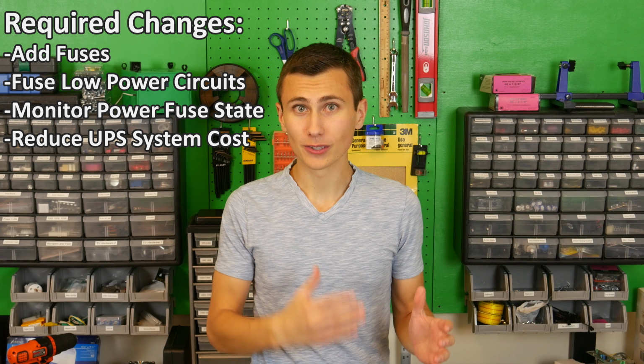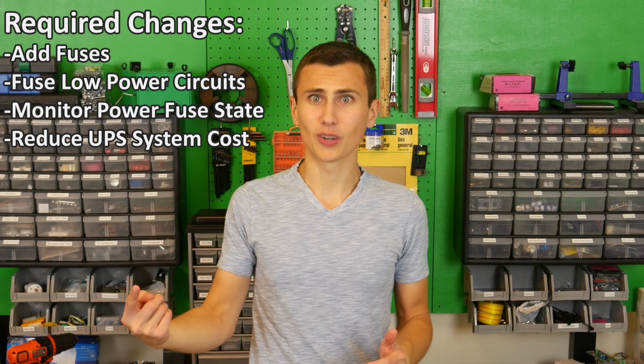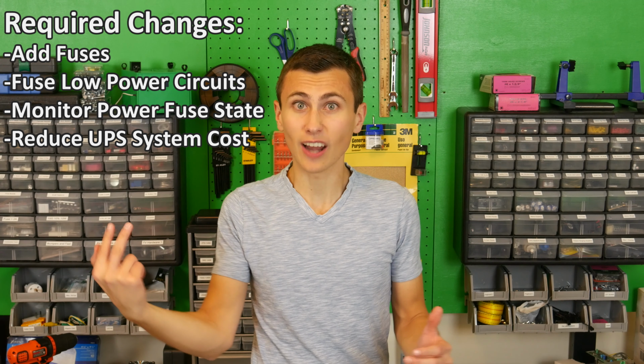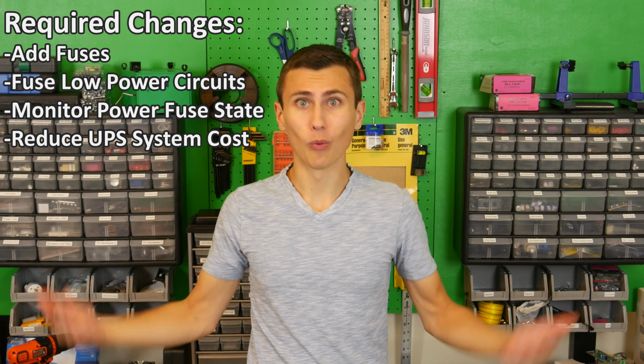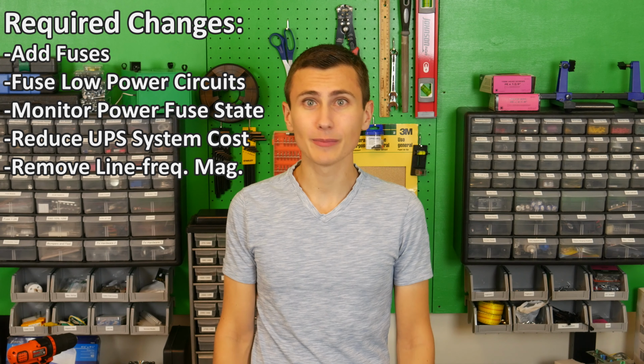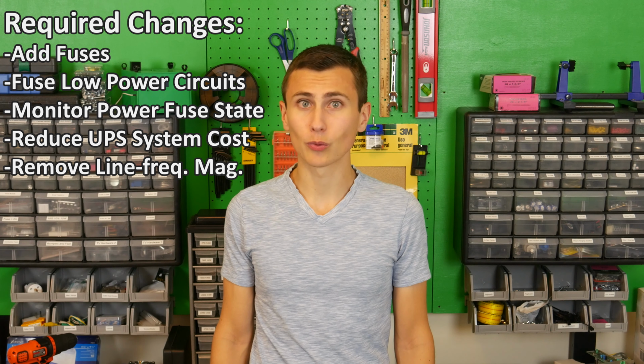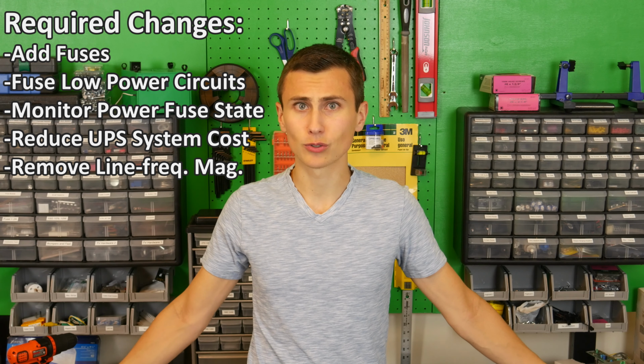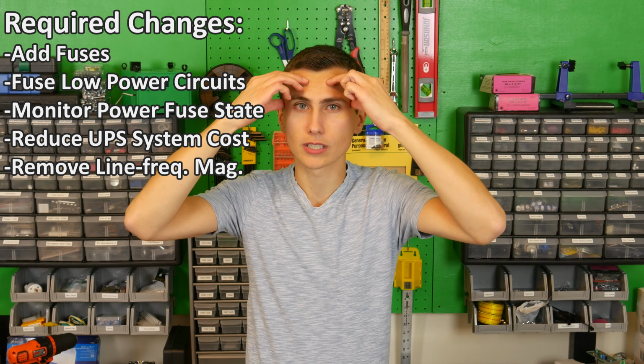Our 500 watt UPS architecture both wasn't going to work and was going to cost $800 per unit. Why? Well, we used line frequency magnetics, which were huge, rated for the wrong voltage, didn't have a high enough turns ratio, and cost $200 each.